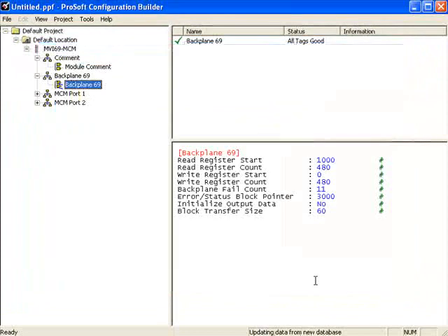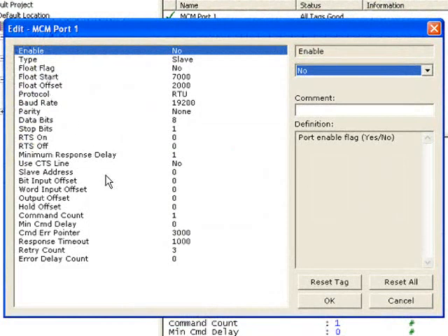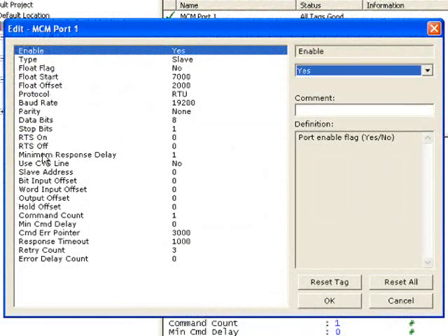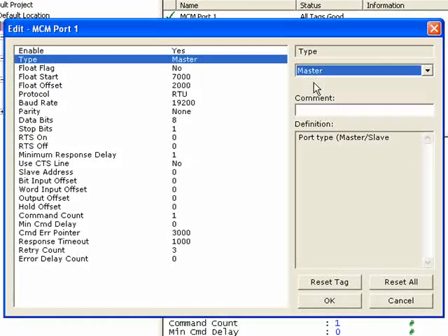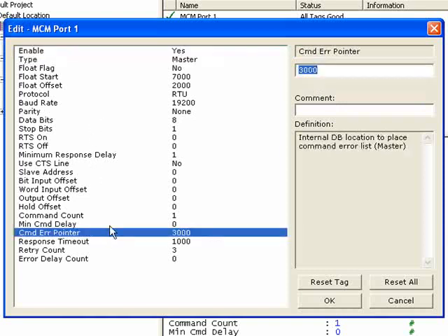Click OK, then click on MCM Port 1 and double-click to open it. Now we have all the parameters for port 1. We see baud rate settings and protocol. You define whether the port is enabled and whether it's going to be a master or slave. I'm going to click Yes to enable the port, then set the port type to master. I'll go to Command Error Pointer and change it to 1400, then click OK.